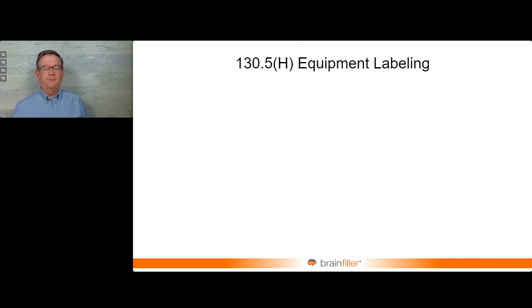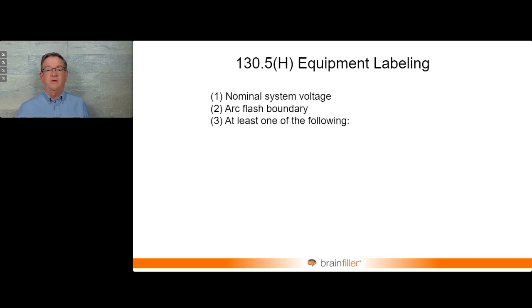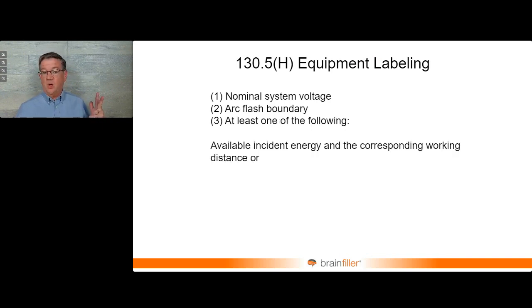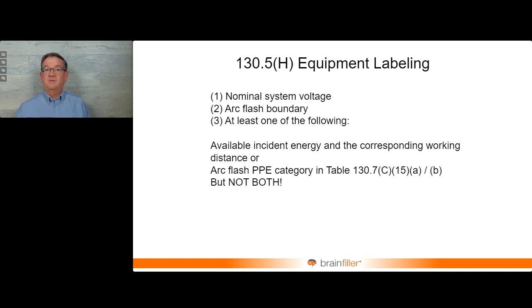Equipment labeling. There was an addition to the equipment labeling requirements, 130.5(H). You have to have the system voltage, the arc flash boundary, and at least one of the following: the incident energy and working distance, or the PPE category. There's a long history behind that one that I won't get into here. But instead of the PPE category, since you're not allowed to link it with the incident energy, do your own. Come up with what's called a site-specific level.